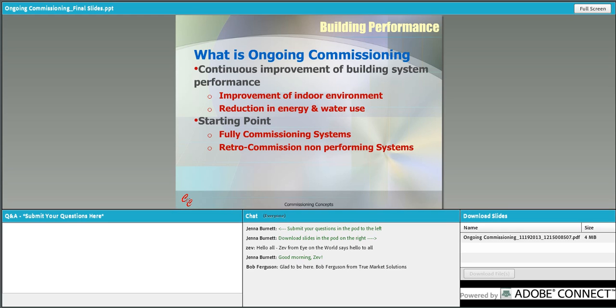Now, if you've got a new building and it turns out that not everything has been done correctly through the process and there are still some things that are not working correctly, and most of you building managers will understand that perfectly, well, then you simply do a small retro-commissioning project on the features of the systems that are not functioning and bring them into a normal, good operating procedure so you can start an ongoing commissioning process. So ongoing commissioning can be launched in a brand new building and it can be launched in an existing building because the processes are the same.